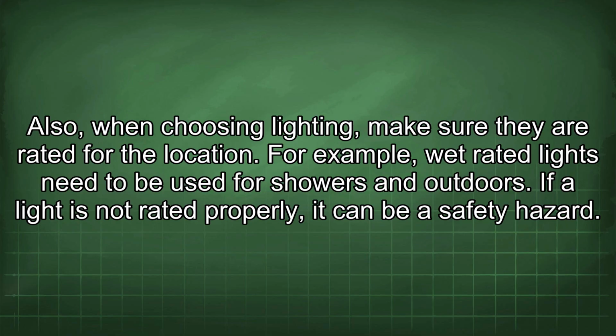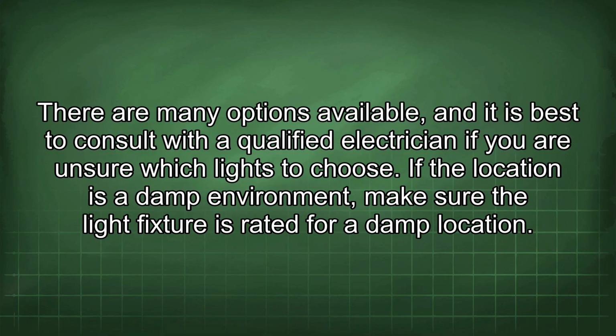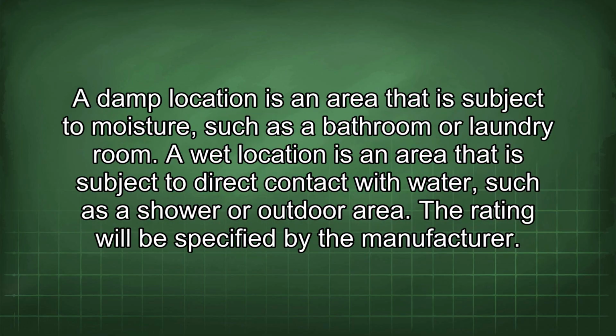Also, when choosing lighting, make sure they are rated for the location. For example, wet-rated lights need to be used for showers and outdoors. If a light is not rated properly, it can be a safety hazard. There are many options available, and it is best to consult with a qualified electrician if you are unsure which lights to choose. If the location is a damp environment, make sure the light fixture is rated for a damp location. A damp location is an area that is subject to moisture, such as a bathroom or laundry room. A wet location is an area that is subject to direct contact with water, such as a shower or outdoor area. The rating will be specified by the manufacturer.